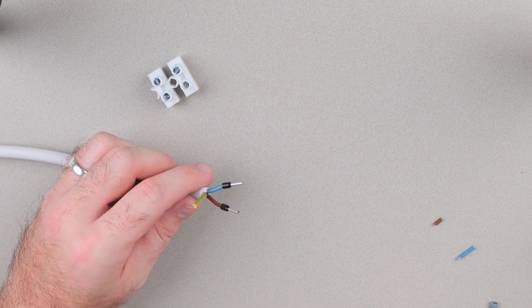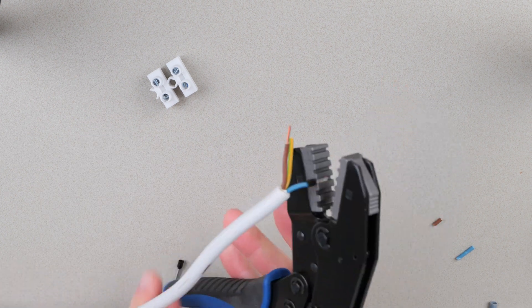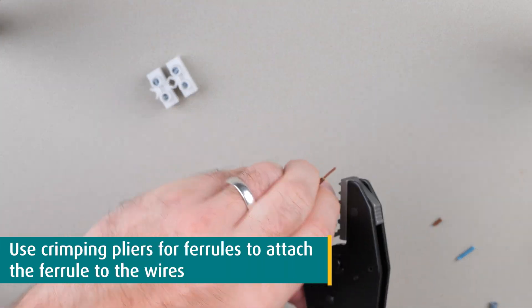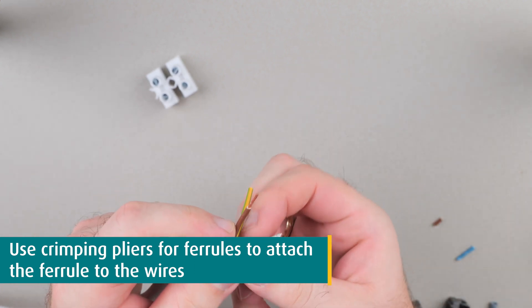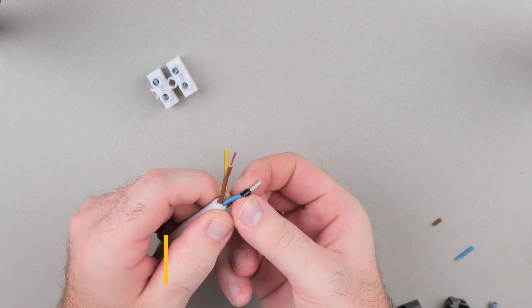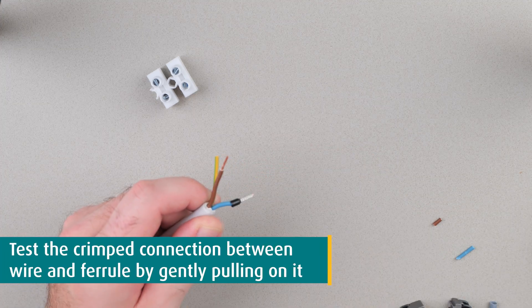Use the correct cross sectional profile of the crimping pliers and press it firmly. If you use automatic pliers like this one, it will lock itself until you've applied sufficient force. When crimped, check the connection by pulling on the ferrule to make sure that it fits tightly and doesn't come off.